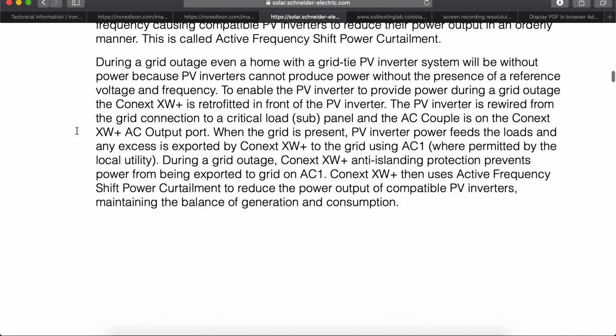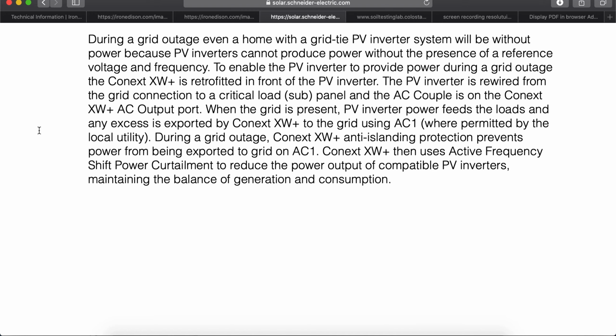During a grid outage, even a home with a grid-tied PV inverter system will be without power because PV inverters, so solar PV inverters, cannot produce power without the presence of a reference voltage and frequency. This is to protect those line people. It's not going to make power. The solar inverter is not going to make power if the grid is not present.